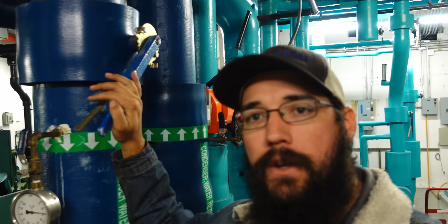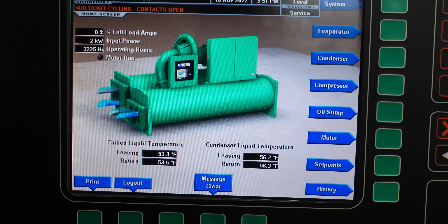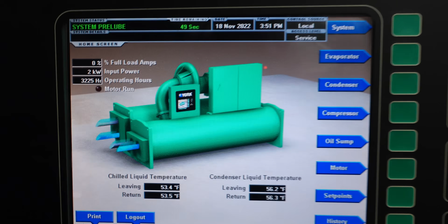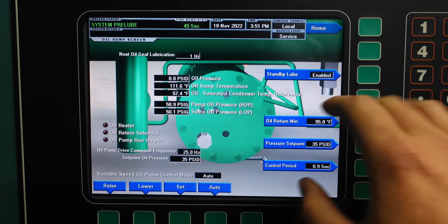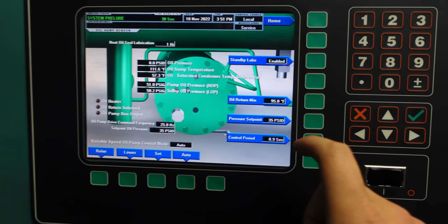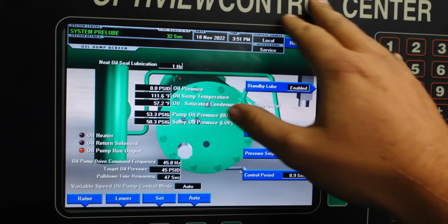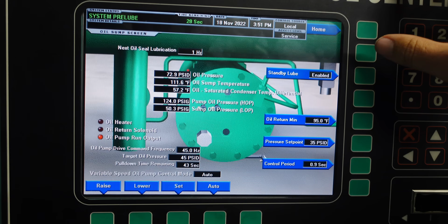We will need to calibrate some things, make sure that everything is tuned in where it needs to be, so we'll go through that once we get done up there. All right, it is the moment of truth. Kick over, hit go. All right, we got pre-lube. Let's go to our oil. So the thing I mentioned we need to do a calibration on is the refrigerant liquid level sensor. The old sensor was bad. We were able to verify that as we were replacing it. So during the recovery process, it was still showing we had liquid level when we absolutely did not.